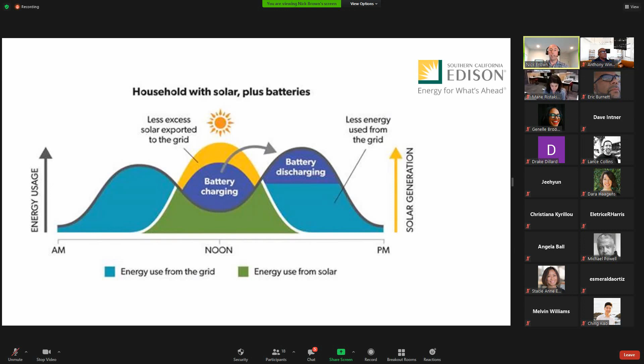As we said before, our solar systems don't produce power in case of a blackout unless you have it hooked into a battery, and you've specifically wired that battery so it can island, so it can operate in isolation from the grid. So make sure if you're working on a battery project, you design this in—an islanding inverter, typically driving a critical load panel that'll stay on in case of a blackout or a natural disaster.